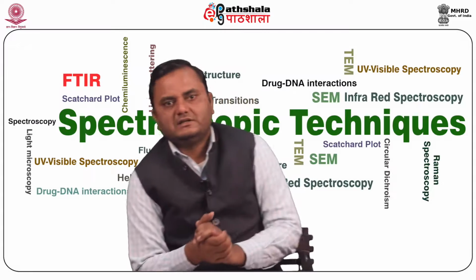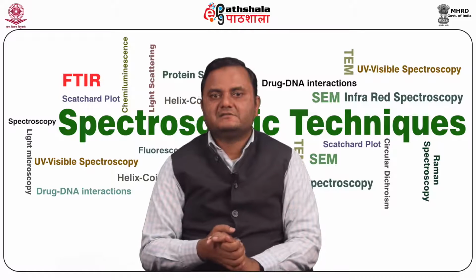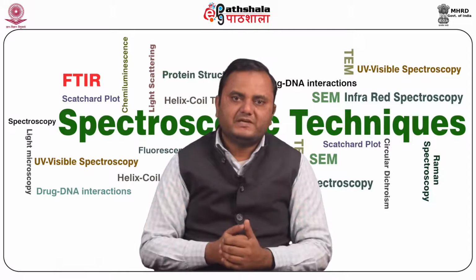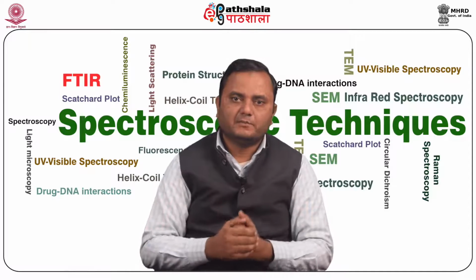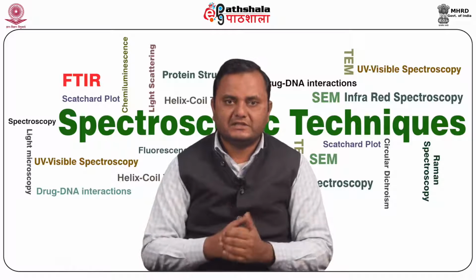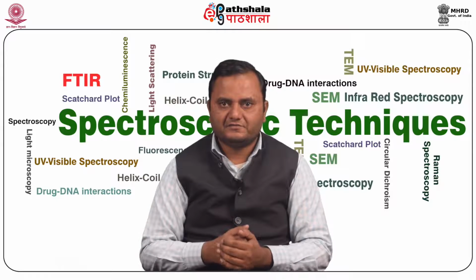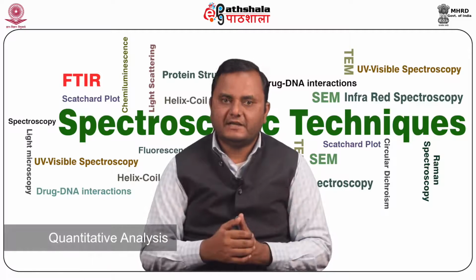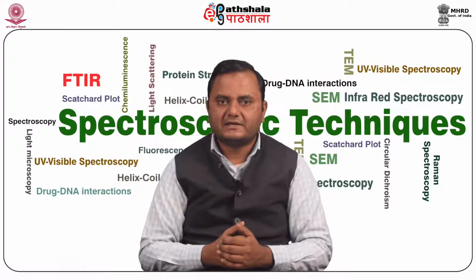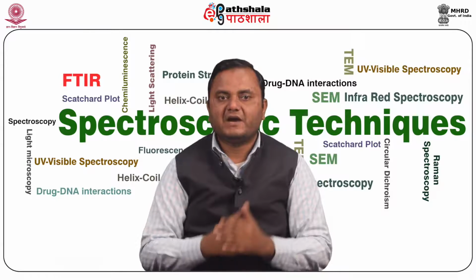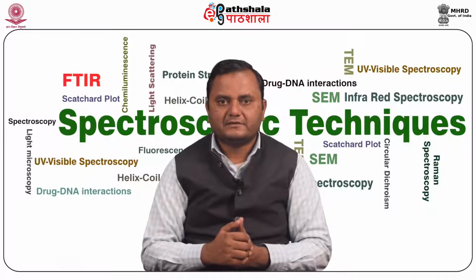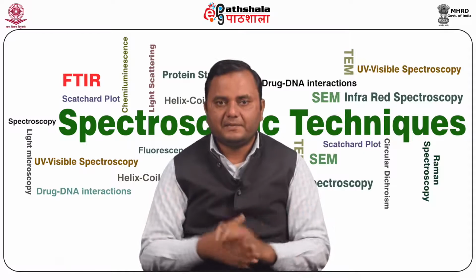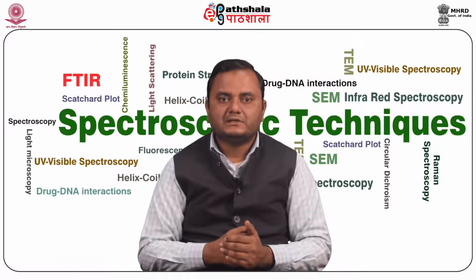Now we talk about the components of IR instruments. The dispersive instrument has a monochromator and is used in the mid-IR region for spectral scanning and quantitative analysis. The Fourier transform IR system is widely applied and quite popular in far-IR and mid-IR spectrometry.